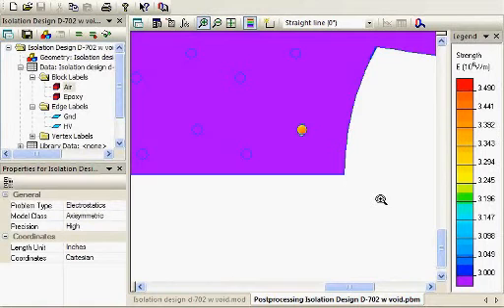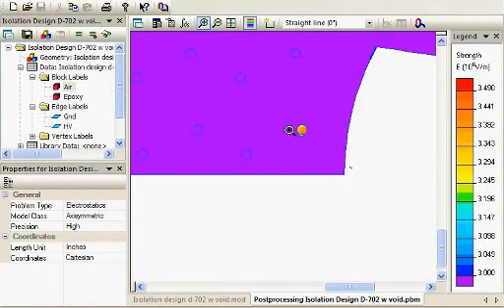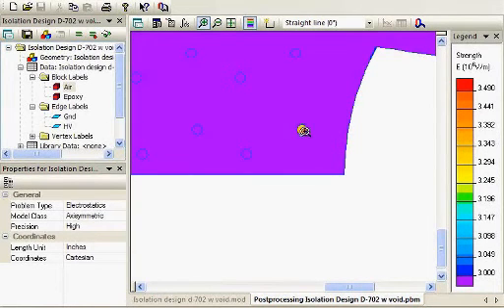But, this one down here is definitely up above the three megavolts per meter field strength. And, so, if that's strictly air at atmospheric pressure inside this void, that's going to start seeing onset of corona or partial or even full discharge.